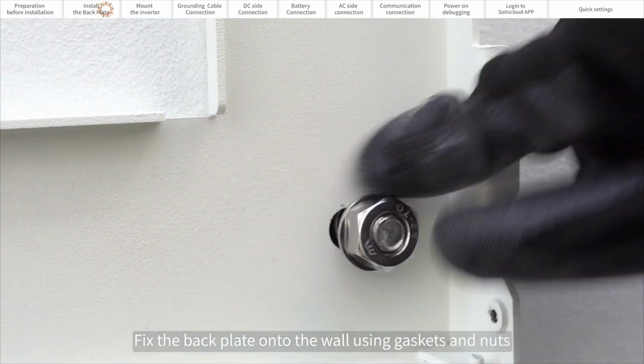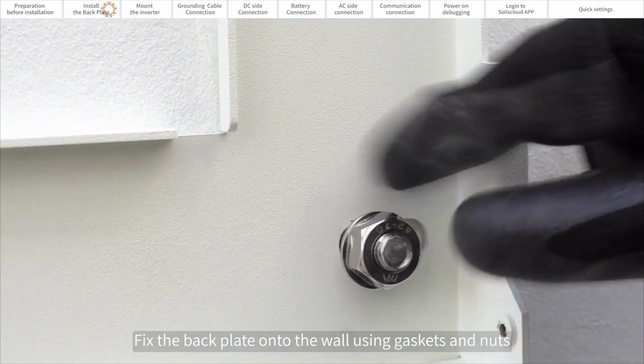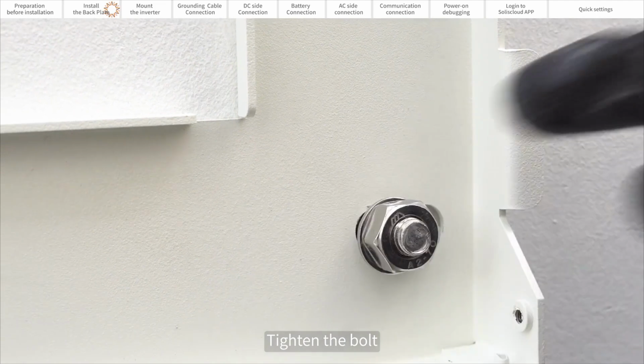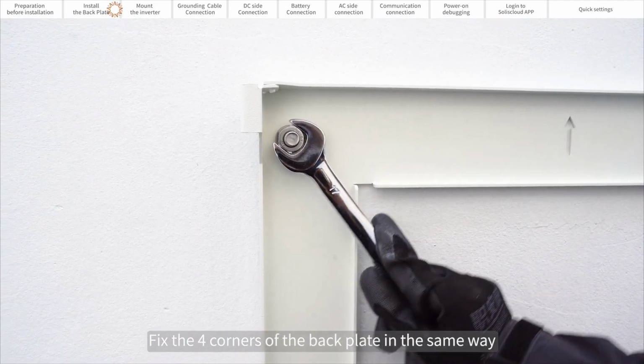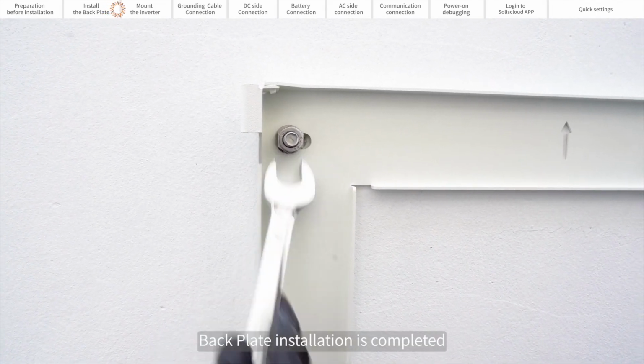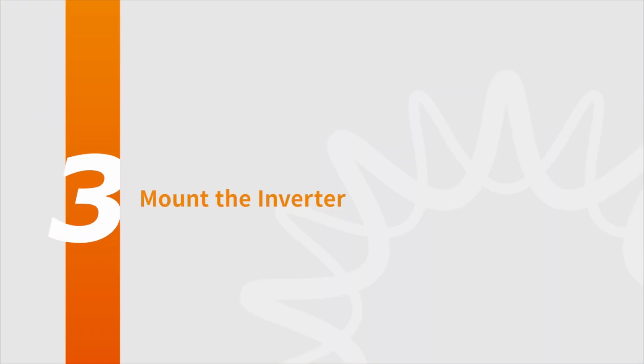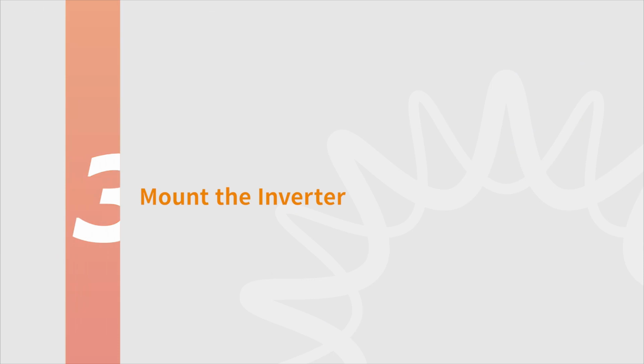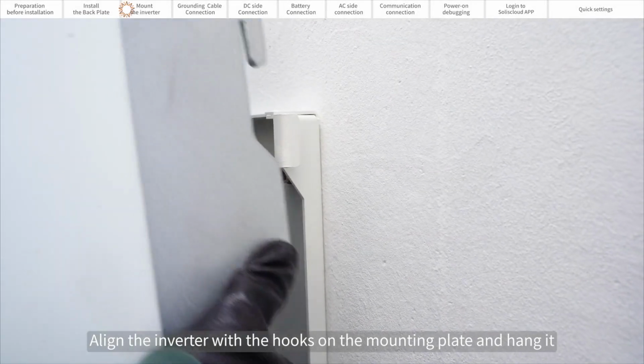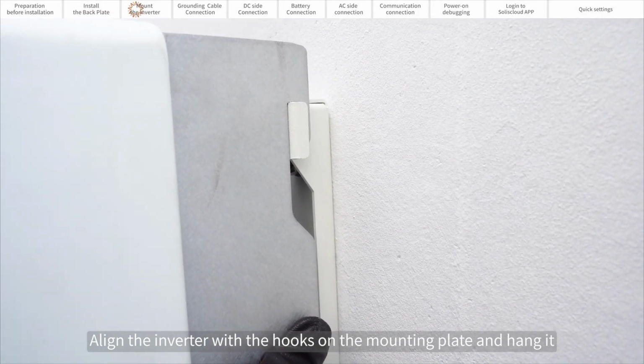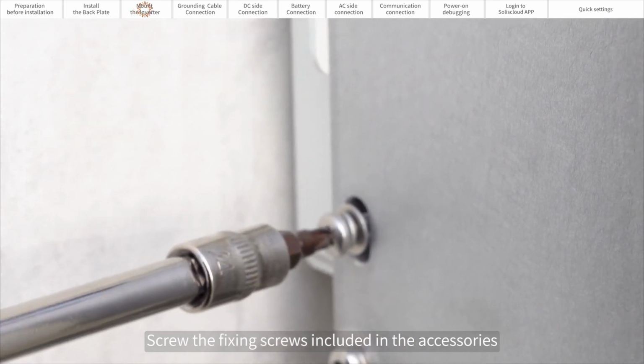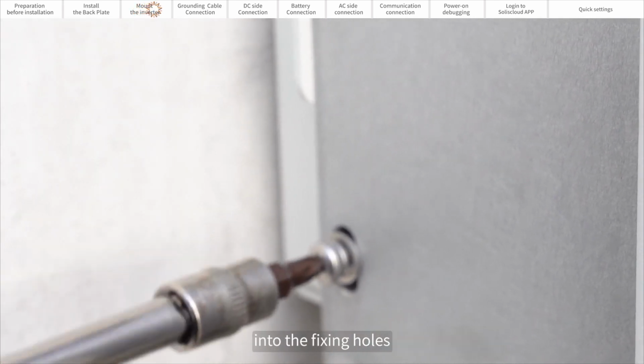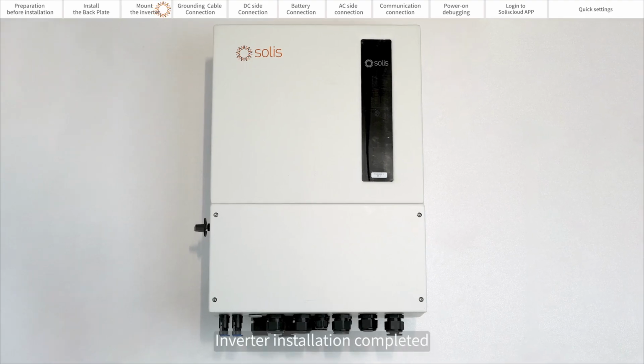Fix the backplate onto the wall using gaskets and nuts. Tighten the bolts. Fix the 4 corners of the backplate in the same way. The backplate installation is complete. Part 3. Mount the inverter. Align the inverter with the hooks on the mounting plate and hang it. Screw the fixing screws included in the accessory bags into the fixing holes. The inverter installation is complete.